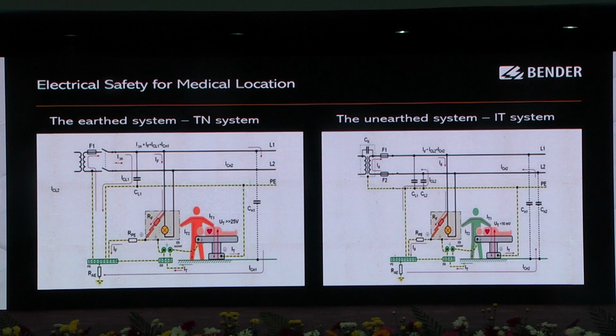So I just want to explain here. The TN system has already been explained by Gopakumar sir and Appu sir. Whenever the system is an earthed system, you can see the secondary side of the neutral is grounded. So during operation, if doctors and nurses touch any live cable, they will get a shock, because the return current will flow through the neutral. In the unearthed IT system, the secondary side neutral is floating. So on the first fault, if you touch the live cable, they will not get a shock, and the return current will not flow.